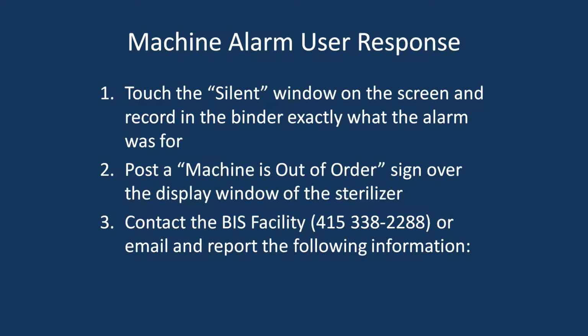Machine alarm user response. Immediately discontinue the use of the autoclave machine if it is not working properly. Touch the silent window on the screen and record in the binder exactly what the alarm was for. Post a "machine is out of order" sign over the display window of the sterilizer.